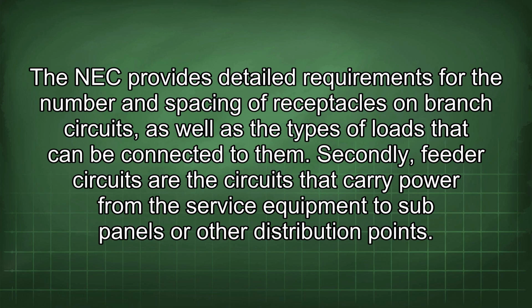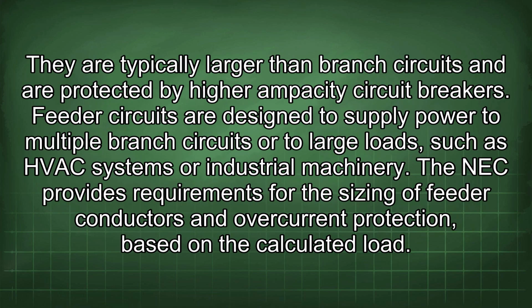Secondly, feeder circuits are the circuits that carry power from the service equipment to sub-panels or other distribution points. They are typically larger than branch circuits and are protected by higher ampacity circuit breakers. Feeder circuits are designed to supply power to multiple branch circuits or to large loads, such as HVAC systems or industrial machinery. The NEC provides requirements for the sizing of feeder conductors and overcurrent protection based on the calculated load.